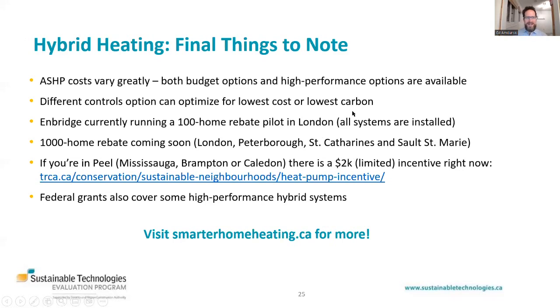Okay, great. Some final things to note on the hybrid heating front. Air source heat pump costs can vary greatly - there are both budget options as well as high performance options available out there. There are different controls for you to be able to optimize for the lowest cost possible, so you might have a higher outdoor temperature switchover temperature, or for the lowest carbon, you could run that heat pump as low as you could possibly get it to.